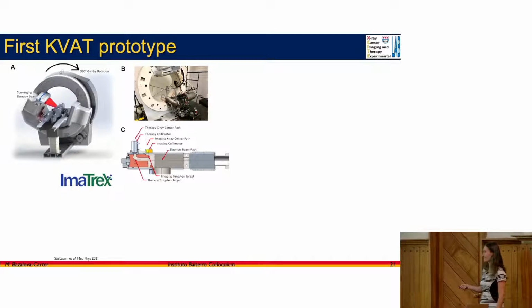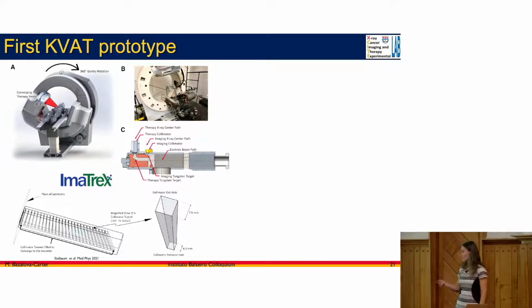And this is the design of the target. So again, it's a reflection target. This is the electron beam source. It's hitting the anode here for treatment. So this is the therapy X-ray path. And they also envisioned, actually, and ran some experimental validation of this beam to have another focal spot for imaging, a much smaller focal spot. So there would be an imaging collimator and an imaging X-ray path. So basically, at the same time, we could be doing imaging and radiation therapy with the same source. So this is the collimator. Remember, our collimator has a number of holes.